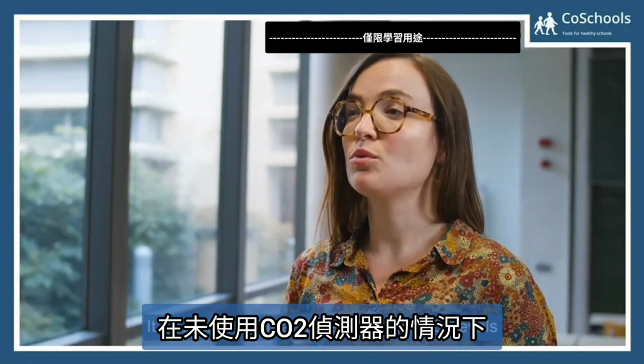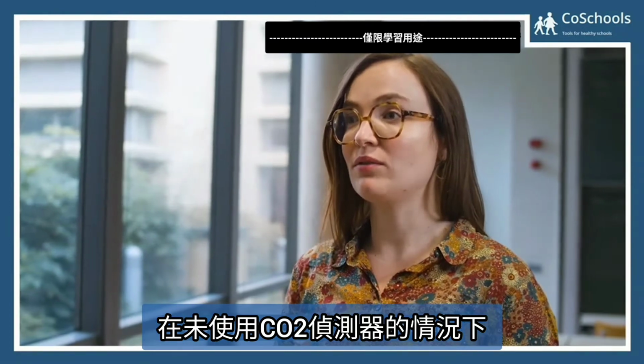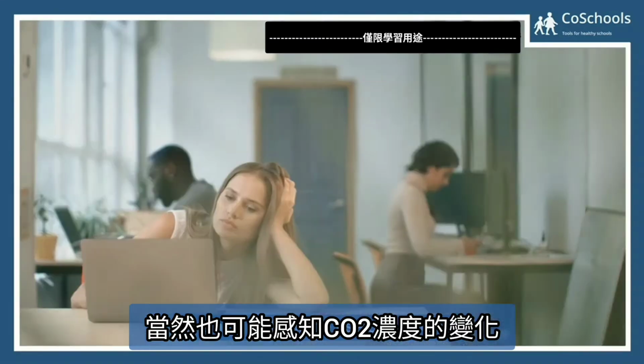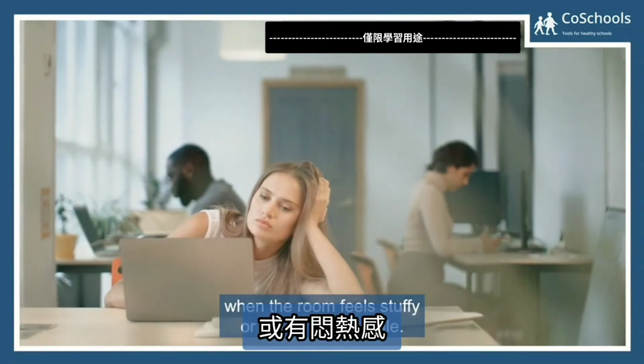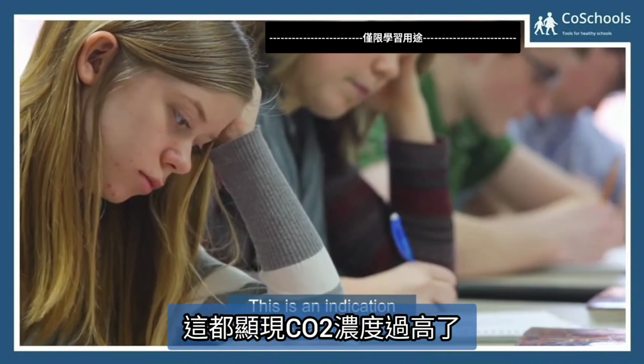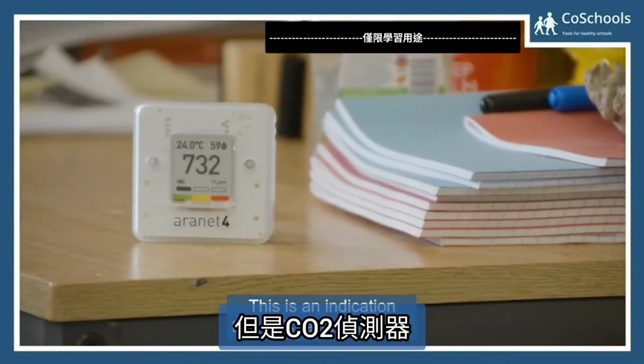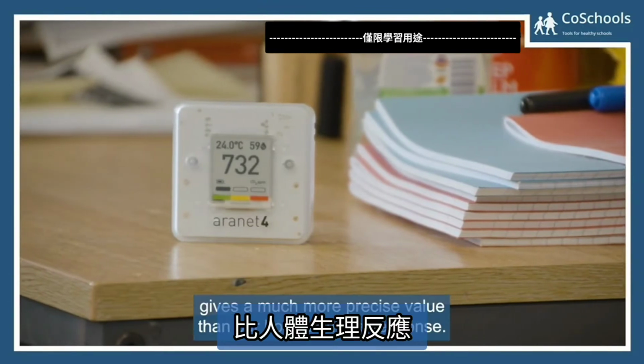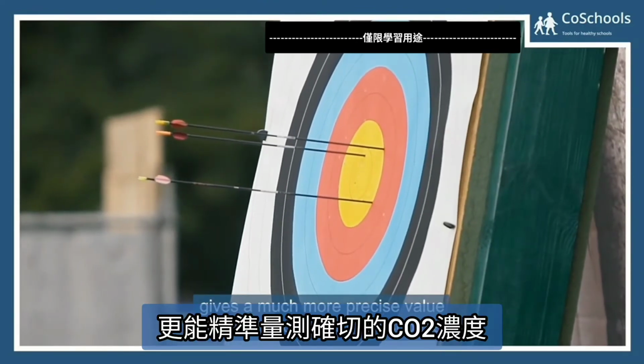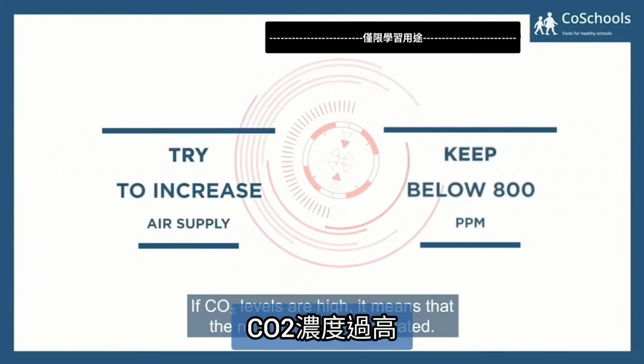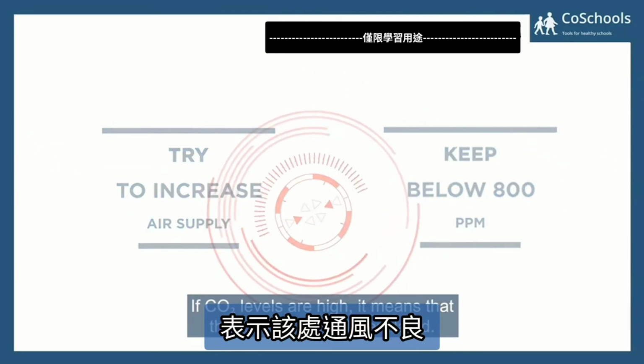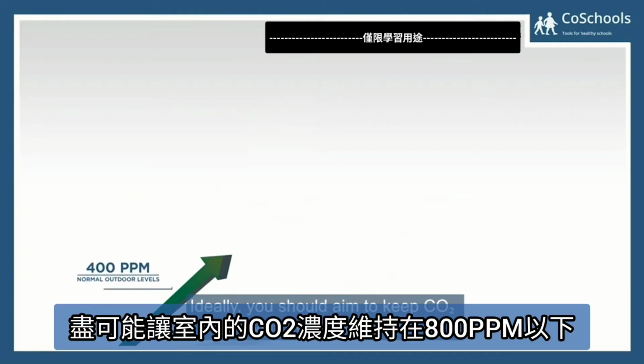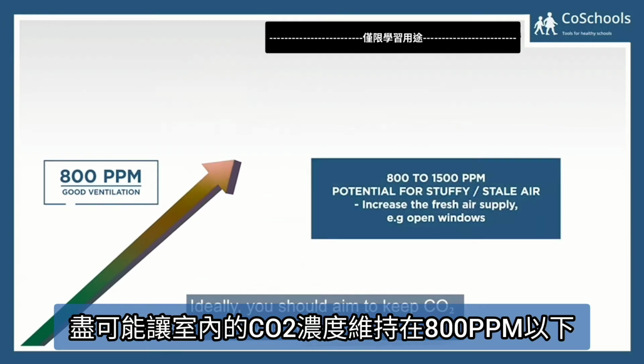It's possible to broadly identify when CO2 levels are high without the use of a monitor. When the room feels stuffy or the air smells stale, this is an indication that CO2 levels are high. The CO2 monitor, however, gives a much more precise value than our body's natural response. If CO2 levels are high, it means that the room is not well ventilated. Ideally, you should aim to keep CO2 levels below 800 ppm.